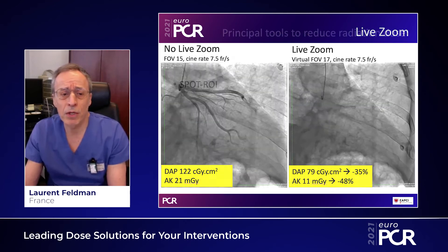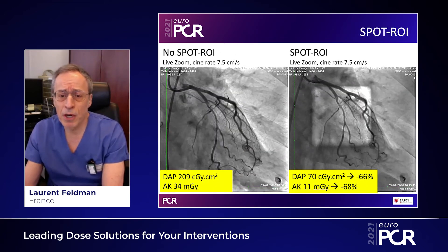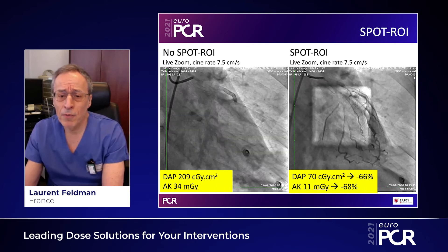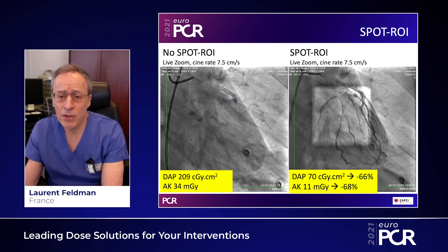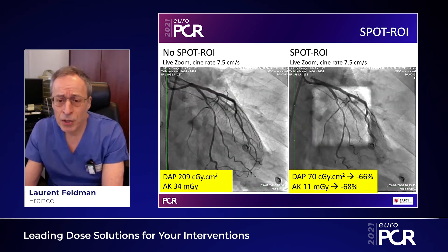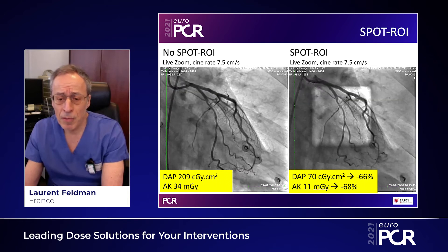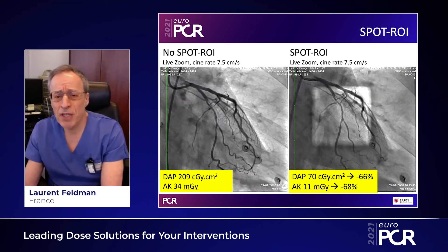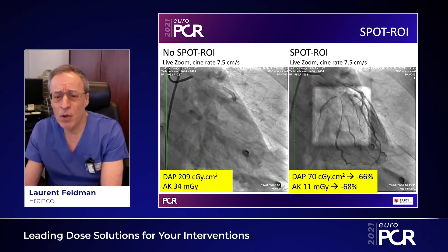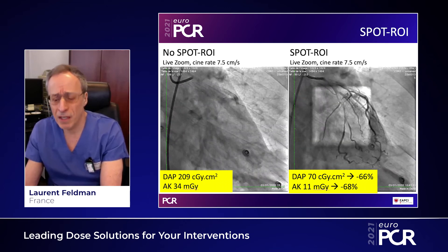SPOT-ROI is another feature which is very unique to the Canon Alphenix Core Plus rooms. The idea is to provide you with a very good definition of an area of interest — in this case, the circumflex artery — but with an attenuation of what is around this area of interest. This allows a dose reduction of more than 60 percent. This is a feature we're using especially in very complex PCIs and CTO, when we know we're going to spend a lot of time and dose reduction is particularly important.